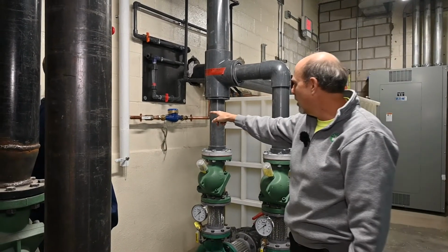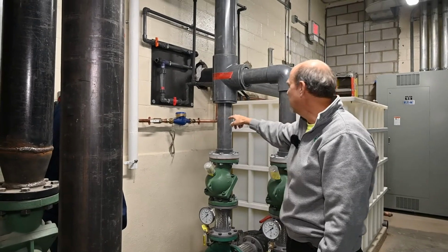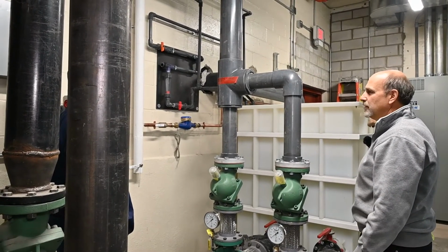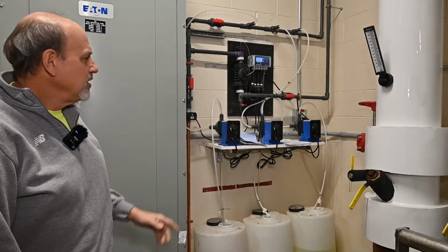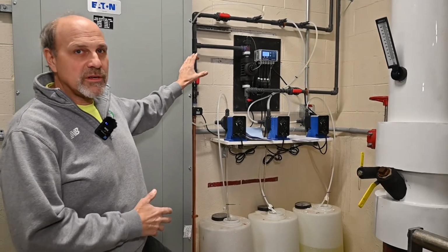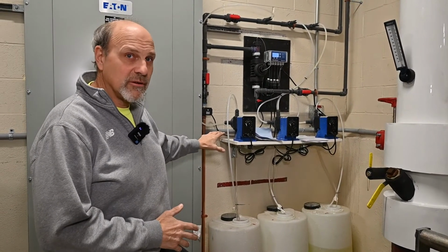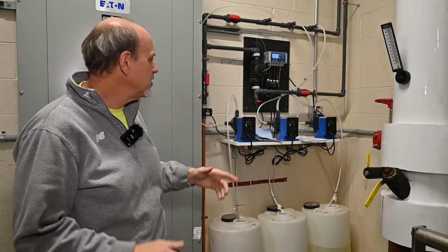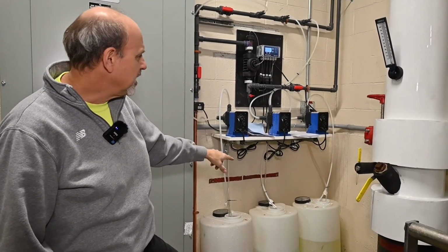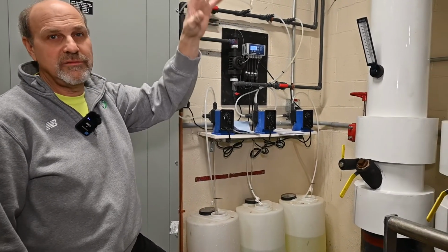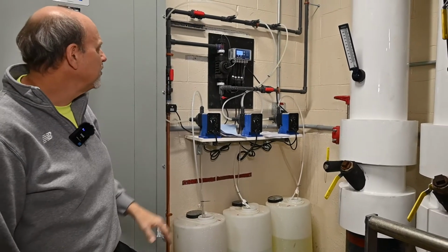This is obviously a water meter as well that's tied to the system, and that'll end up just dumping water into the cooling tower. So this is the other part of the chemical treatment system, strictly for the cooling tower. Nothing to do with your glycol systems at all. There's 3 pumps, 3 different chemicals that maintain the corrosion and conductivity level in the cooling towers themselves.